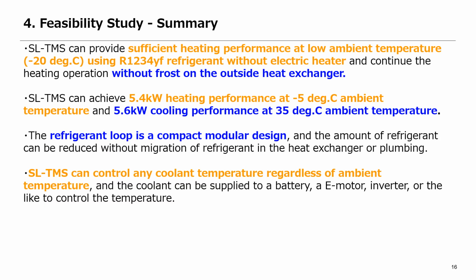This slide offers a concise summary of SLTMS's capabilities. Efficient heating performance. SLTMS achieves notable heating results at low ambient temperatures using the R1234YF refrigerant, eliminating the need for an electric heater. Additionally, it ensures uninterrupted heating without any frost on the outside heat exchanger. Performance metrics. At -5 degrees Celsius ambient temperature, SLTMS delivers a heating performance of 5.4 kilowatts. Conversely, in warmer conditions at 35 degrees Celsius ambient temperature, it provides a cooling performance of 5.6 kilowatts.